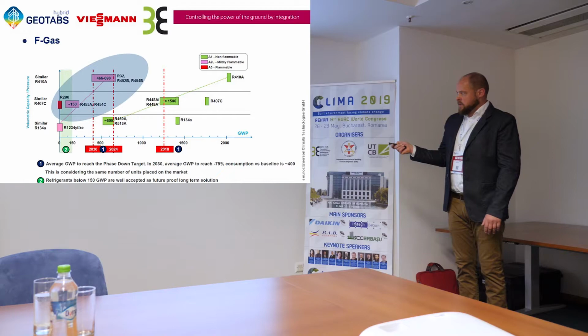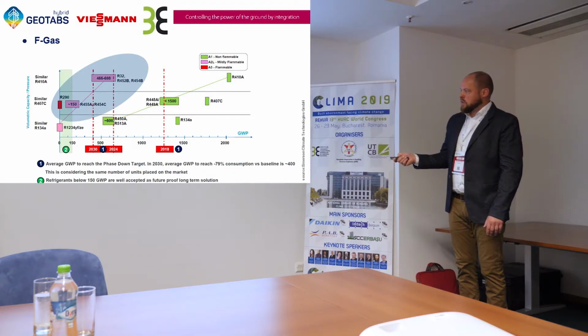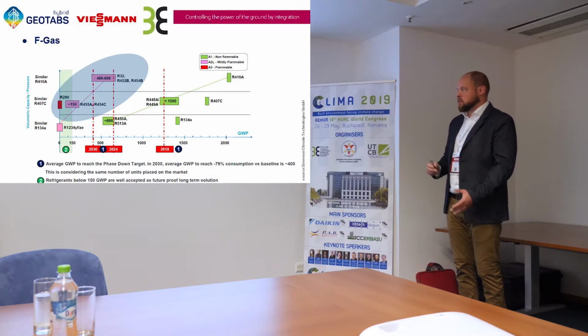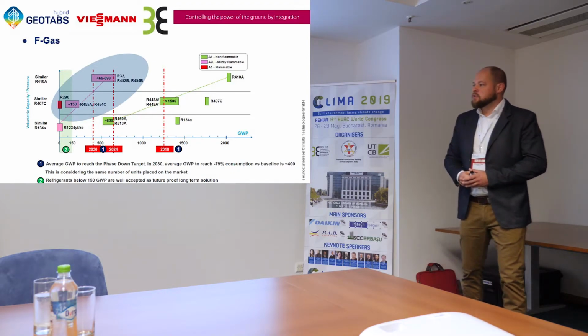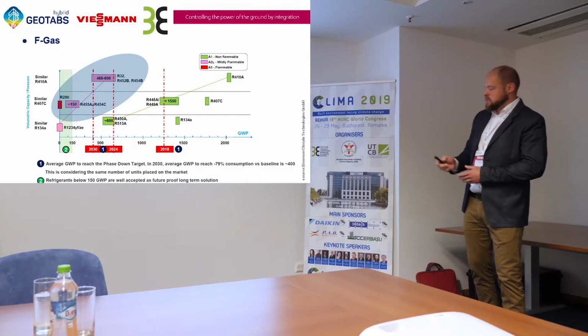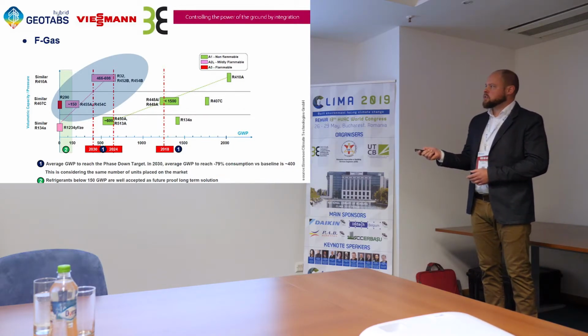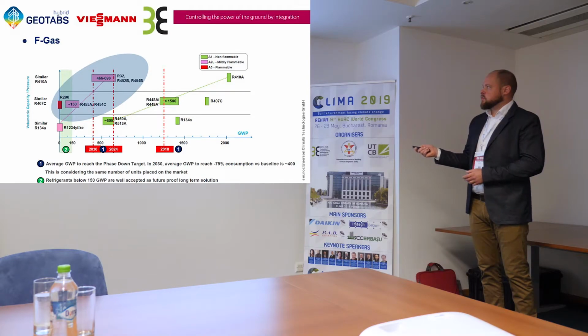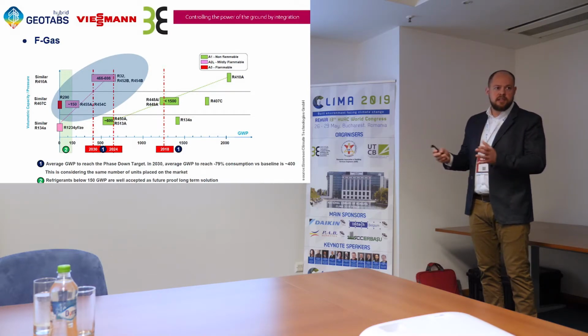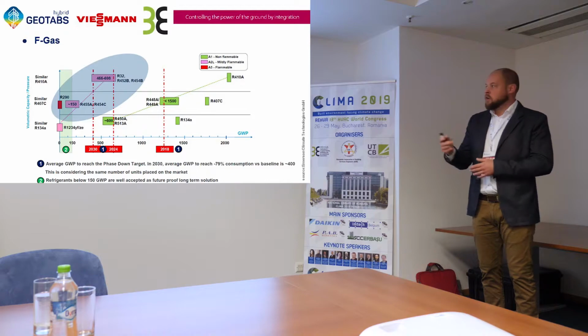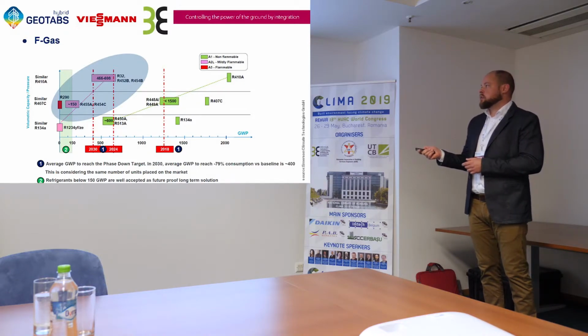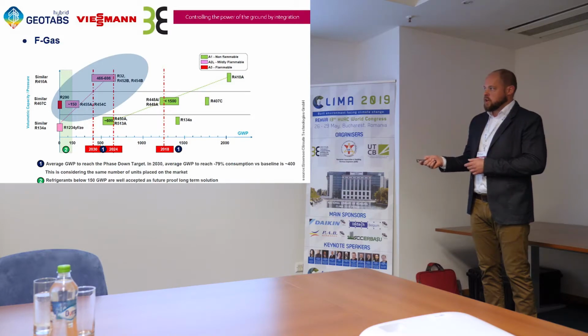What's the development that we see today? So the benchmark for 2018 lies here. We have a number of different alternatives. One alternative used by Daikin, for example, is the R32. R32 is a refrigerant that's already present in the 410A; 50% of 410A is R32. So it's a refrigerant that is well known and can be used today, and it meets the regulations of 2024, for example, you see. But what's the main conclusion?